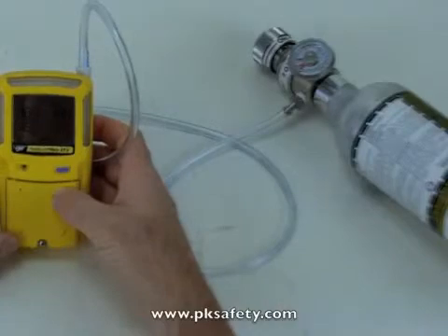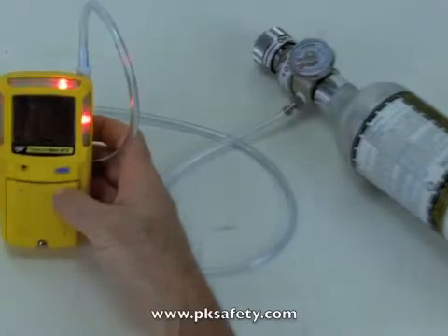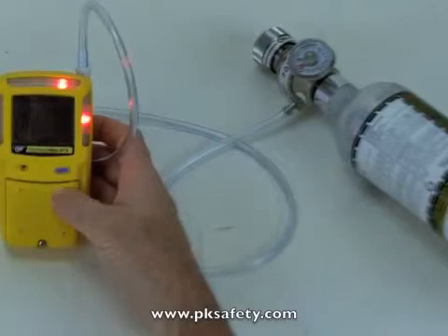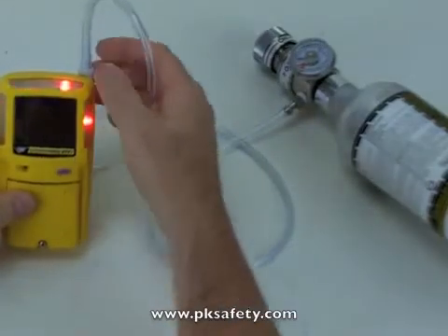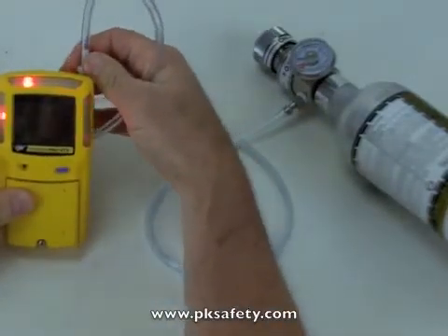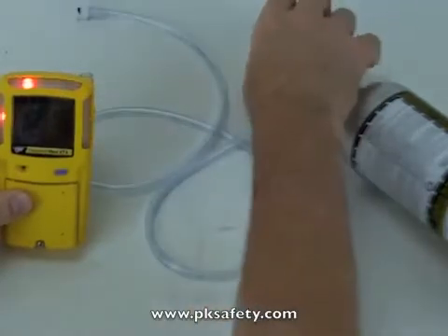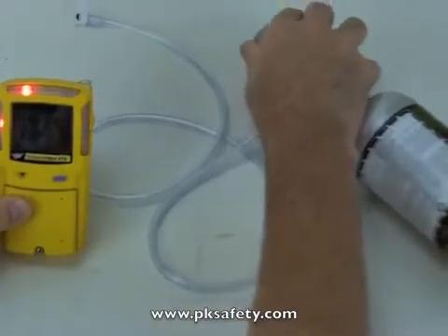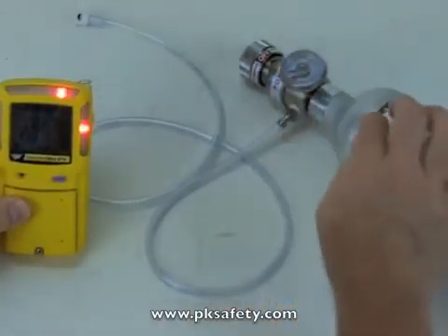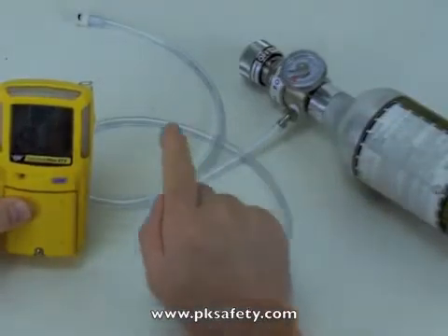All right, so calibration is done. We're all set there. We can now, it's going to tell me to remove this thing. Essentially it's gone into alarm because the cal process is over with. So what I'll do now is just remove this hose off of here and turn off the gas. This is kind of important. Don't forget that, because this gas is ridiculously expensive.